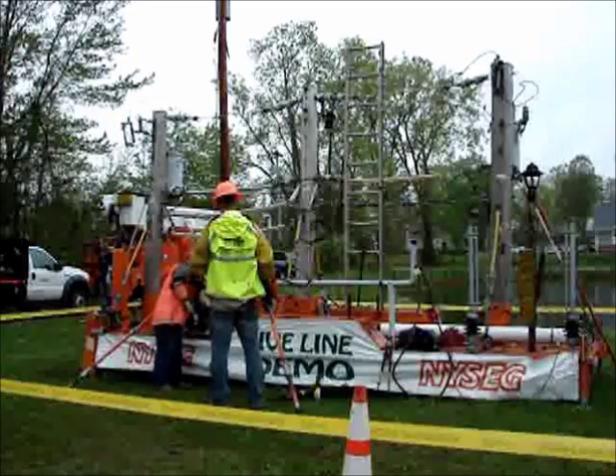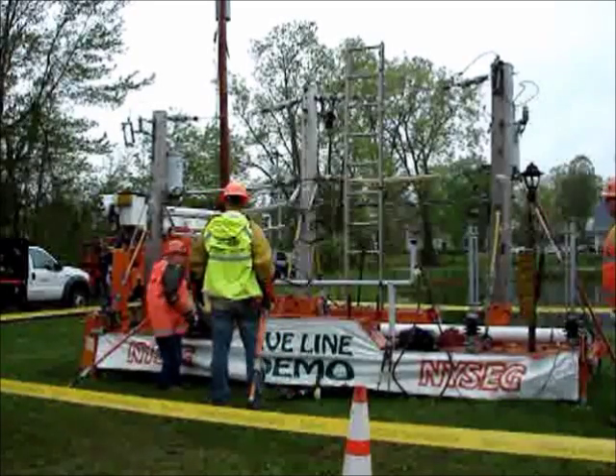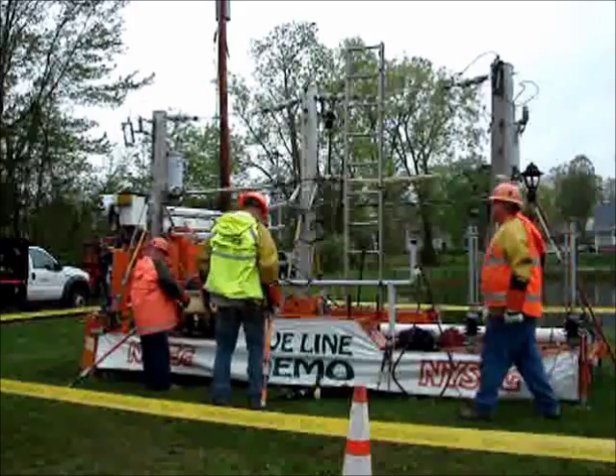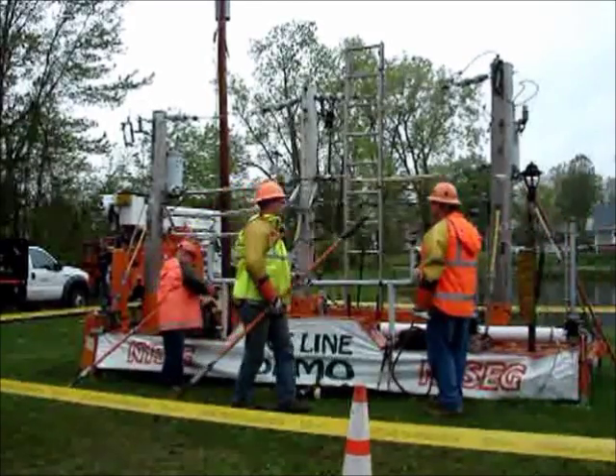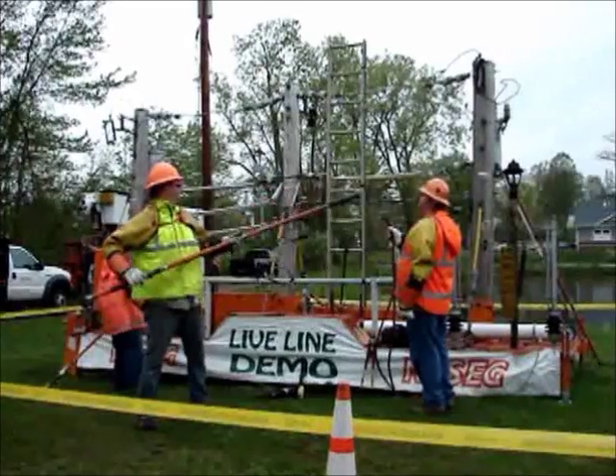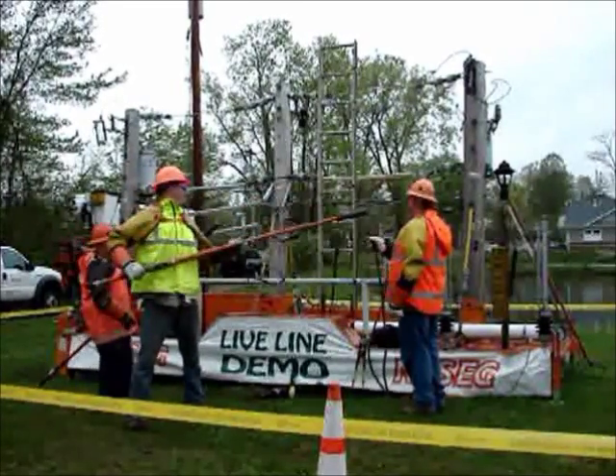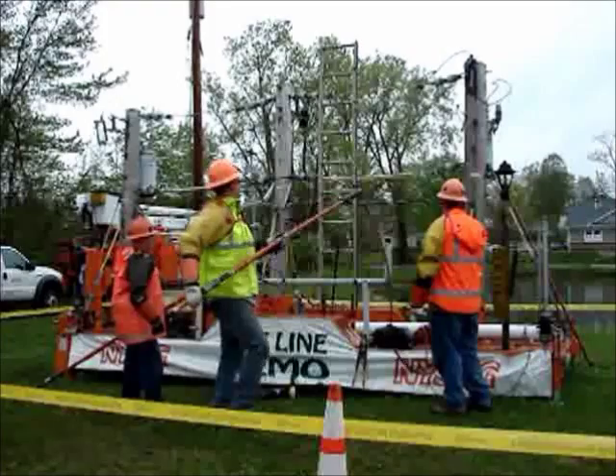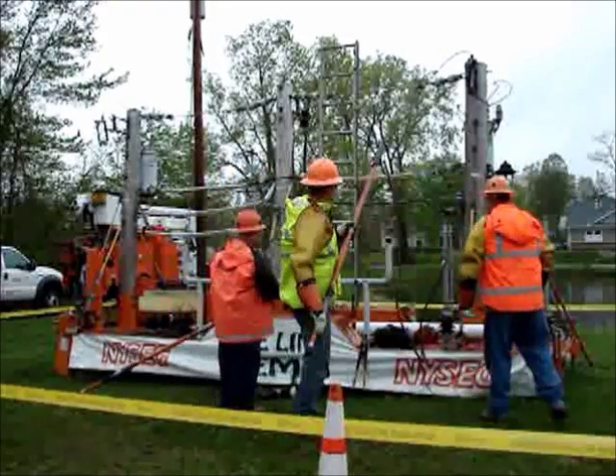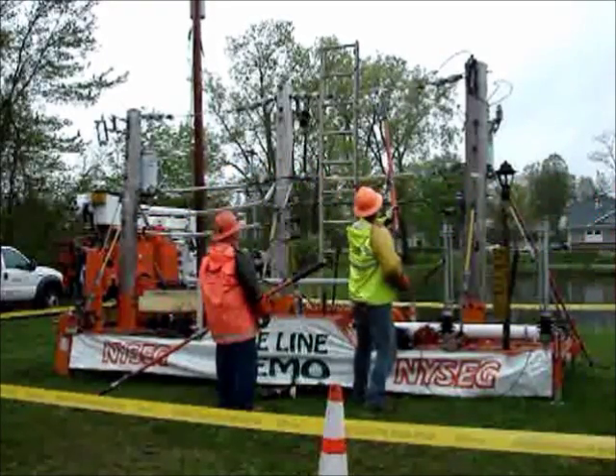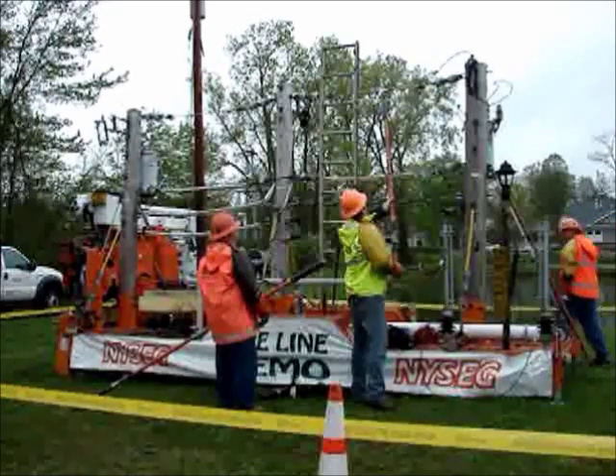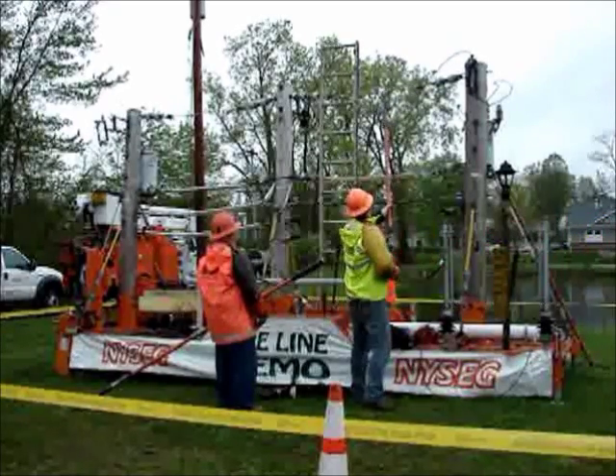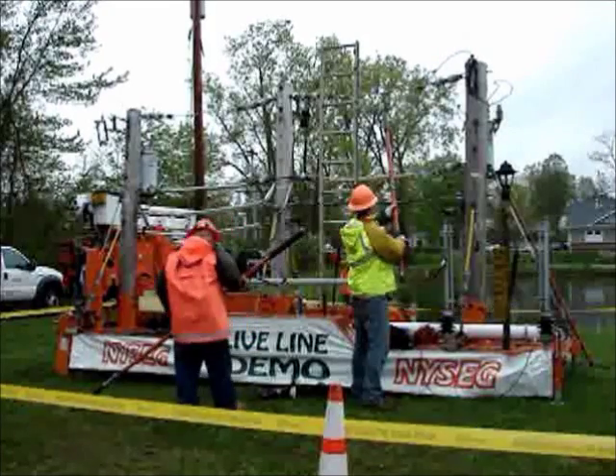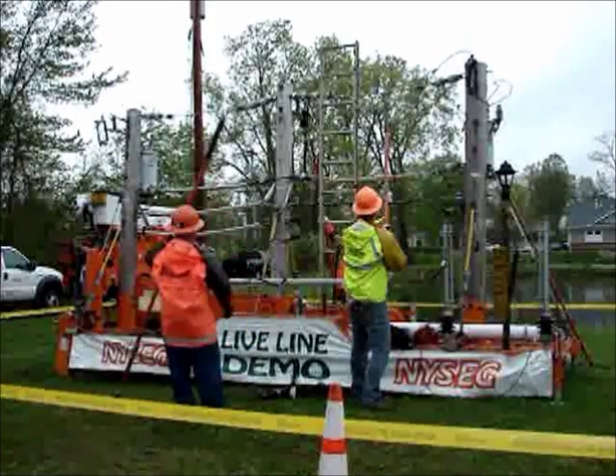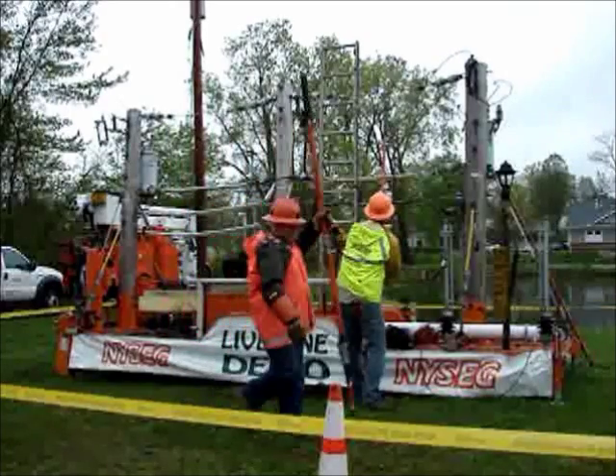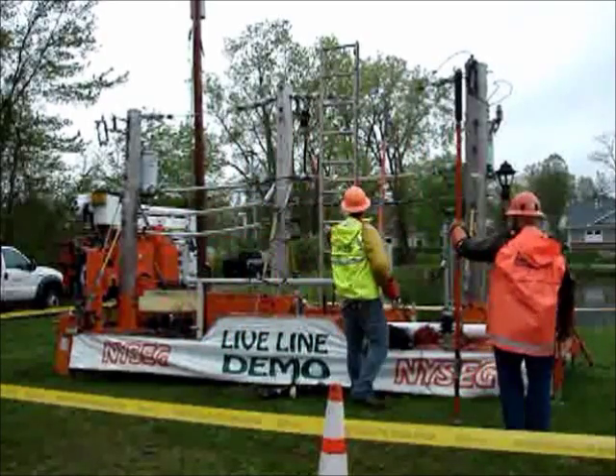The next example we'll do is a primary on a fence. This one is especially important to you guys because you always go out to car accident sites. We have this voltage, 4800 delta, which can lie on the ground for days live and not blow a cutout. So if it's lying on the ground, it can easily lay on a guardrail further down the street from where you are, and it'll just sit there energized. Unlike the 7620 voltage, which will usually blow a cutout, the delta will sit there live and you won't see it — if you touch it, it'll get you.